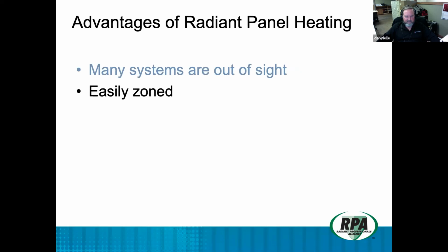Easily zoned. I've had customers that have asked me to make every room an individual zone. He was a stockholder of Uponor, got all of his product basically at cost. And, you know, it's a fantastic system. I don't generally recommend that. I usually recommend a minimum of 3 zones. If they want to go 4, 5, 6, whatever they want, that's up to them. But typically common living areas, uncommon living areas, sleeping areas, and bathing areas. That's the big 4 at a minimum. There should be 4 zones.